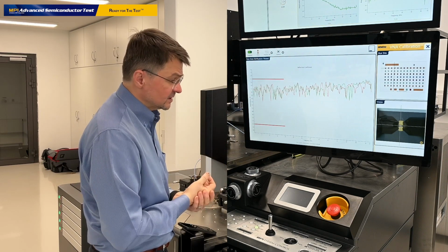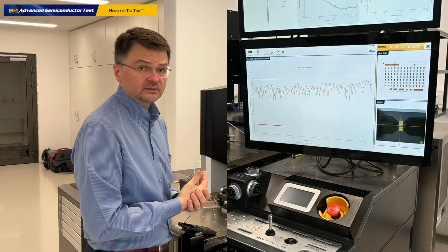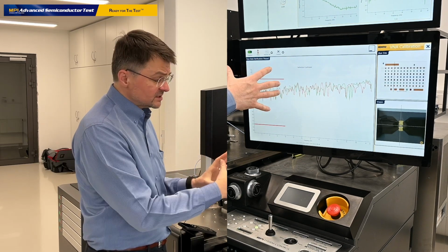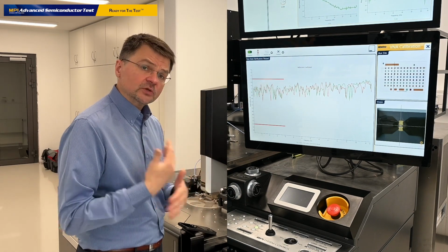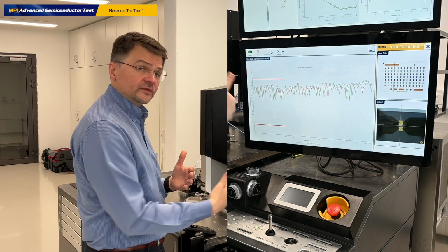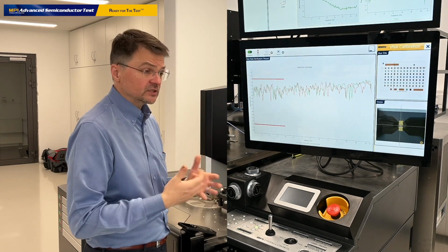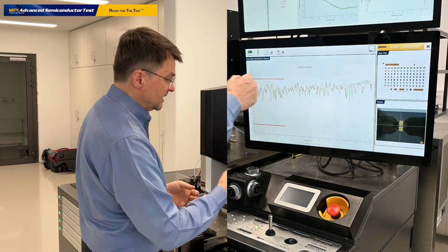Usually this is an operation which we suggest to be done by an experienced engineer who really understands all specifics of the current setup. And once these boundaries are adjusted, they're saved in the QAlibria project, and any inexperienced operator can rely on this data verification process. So if something is wrong with the data, QAlibria will bring a notification that the data are not good, so you need to fix the problem or call an expert.